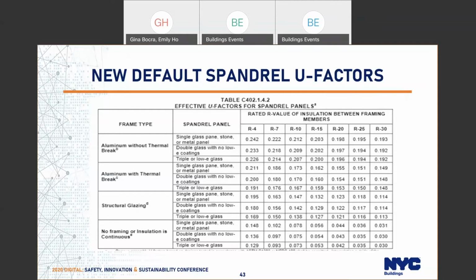It might have triple or low-E insulated glazing. And then in the column to the right, you see the R value of the insulation material that you're using behind that spandrel panel. The lowest R value that you can take into account in this default table is R4, and it goes up to R30. We do not allow you to extrapolate beyond R30. You'll have to do a THERM analysis.